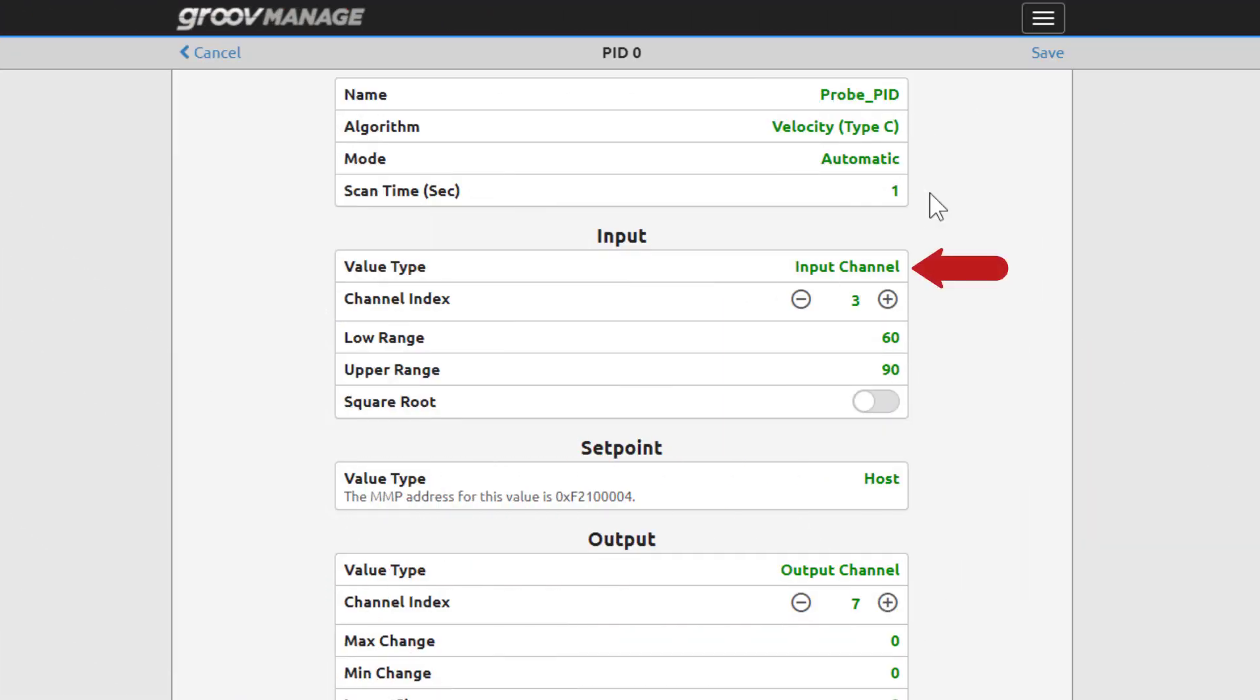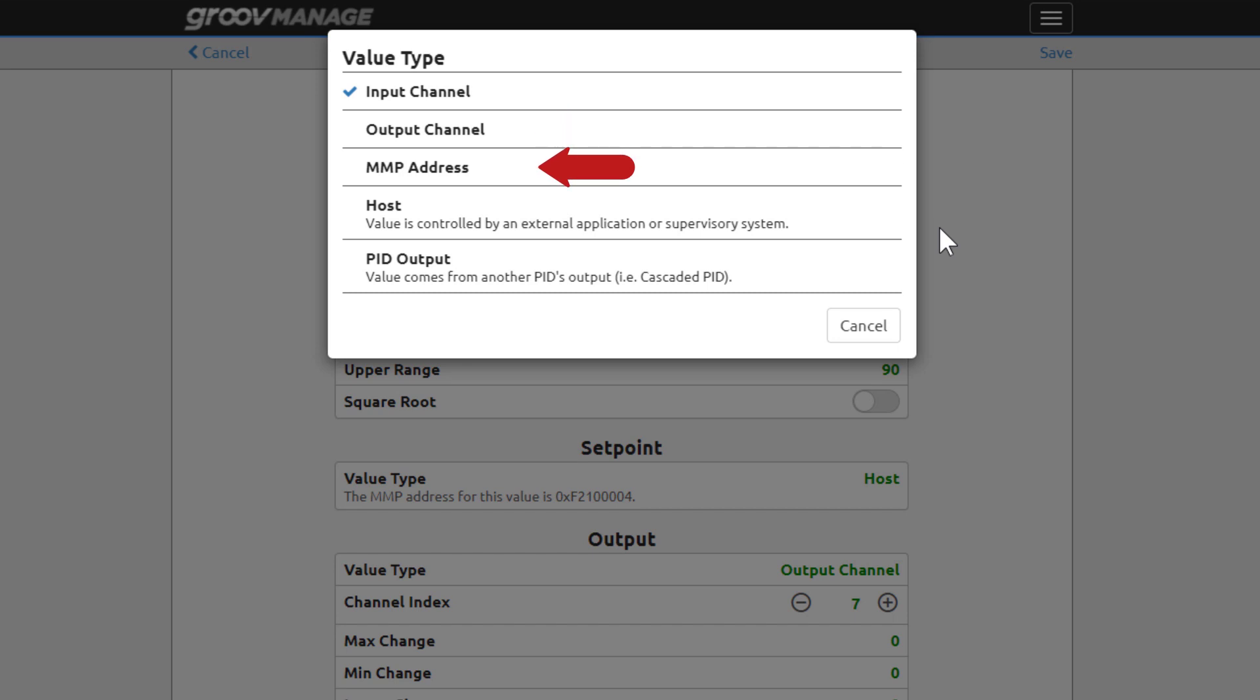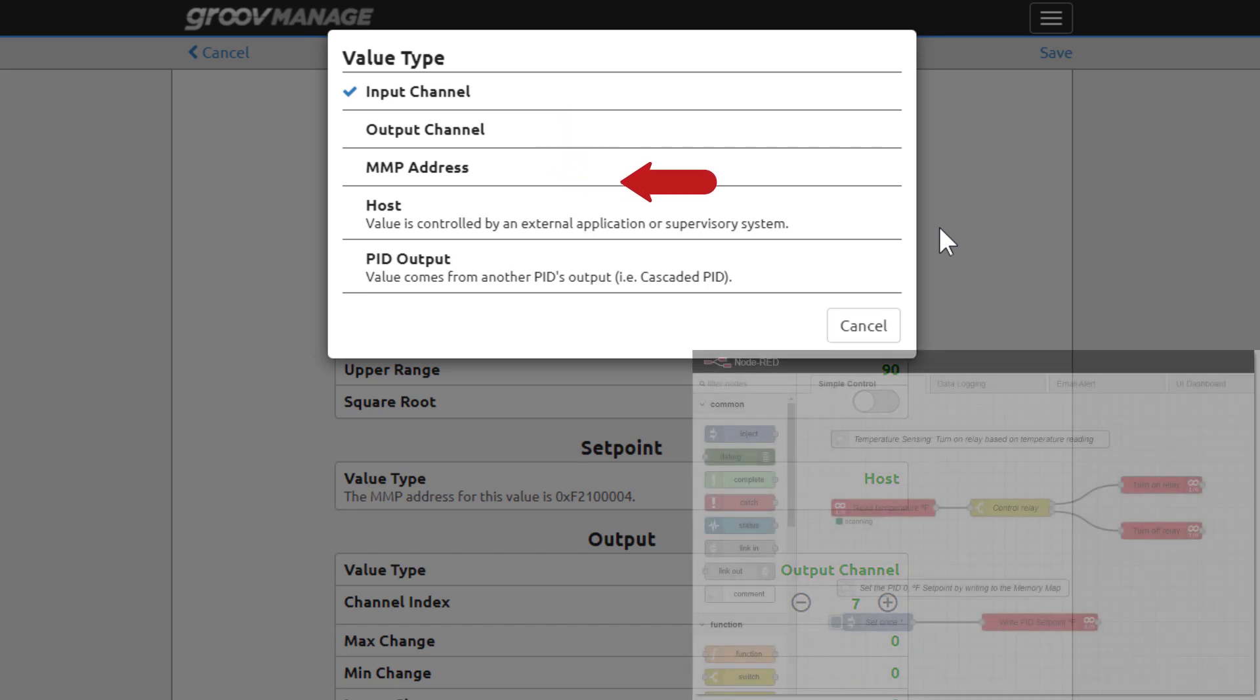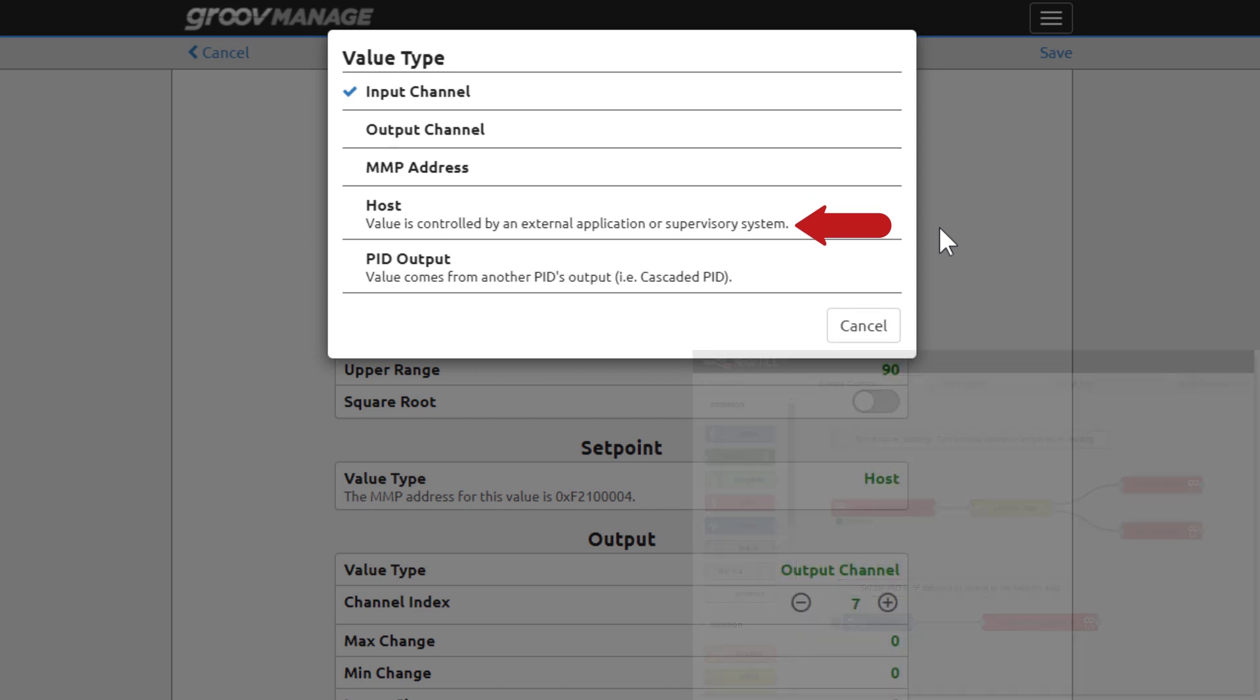The input to the PID can come from different sources. This PID is using an analog input channel, but you could use a value coming from an analog output channel, a memory map address, a control program such as Node-RED, or even another PID. You can also cascade PIDs by simply using the output channel of one PID loop as the input channel for another.